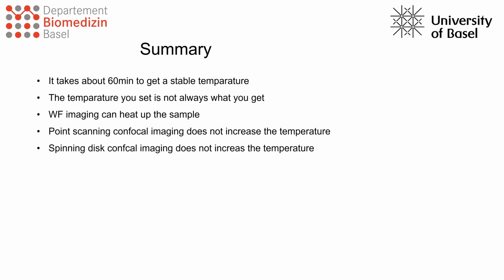So we have to actually compensate there or be careful. And then in terms of illumination, we found that wide field illumination can increase the temperature of the sample, or at least the sample we used there. And also point scanning and also spinning disk confocals didn't change the temperature at all.